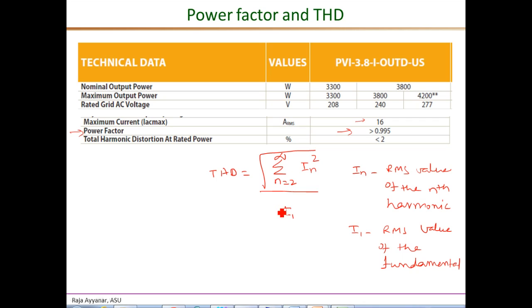For a high-frequency PV inverter, there is very little low-frequency harmonic content if the PWM is well designed and the frequency modulation index is reasonably high. Much of the distortion is related to the switching frequency and its multiples. The type of PWM method used, its design, the switching frequency, and the output filters — whether it's a single L or an LCL filter — together determine the THD in the line current. For this inverter design, the THD is specified to be less than 2%, and this is specified at rated full power.